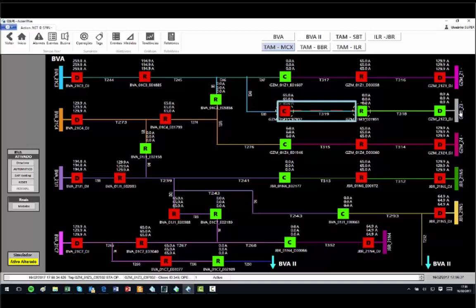The ADMS FLISR module detects the fault and suggests two commands in the maneuvers window, that when executed, isolates the T318 line and re-energizes the T319 line, fed by the blue feeder.